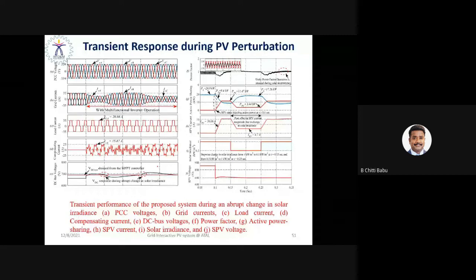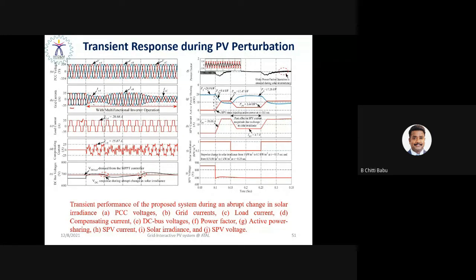You get complete insight on this control. And this is the simulation response: at 0.21 second, we connected a non-linear load, a diode bridge rectifier load, and the grid current is distorted. At this point, we employ the active harmonic or proposed control technique. It shapes your grid current waveform sinusoidal, as it is injecting a compensating current of 15.87 ampere. It eventually eliminates all lower order harmonic components. Moreover, the DC link voltage remains constant and always follows the reference trajectory of 690 volt.